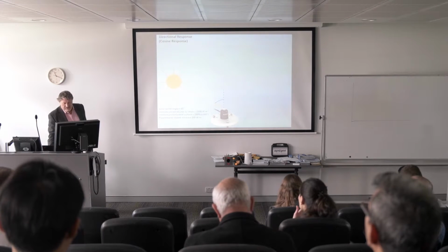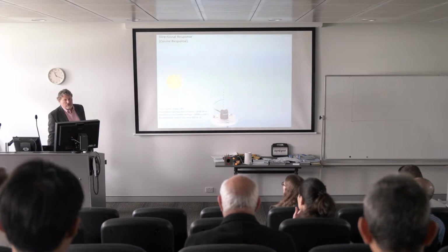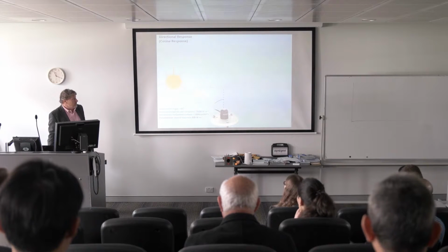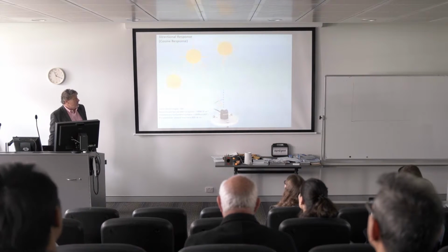I worry about people selling cheap instruments and getting the cosine really wrong. And if you know what you're doing, you can test this compared to a better instrument. But cosine is one of the things that some lower cost manufacturers sometimes forget.